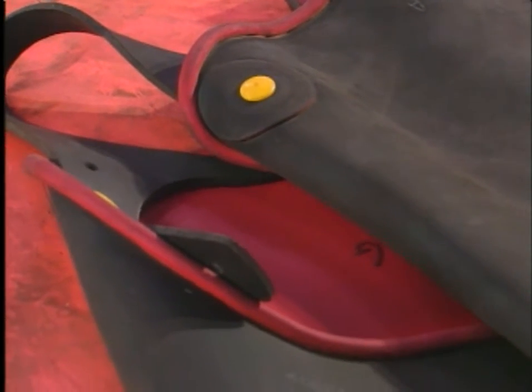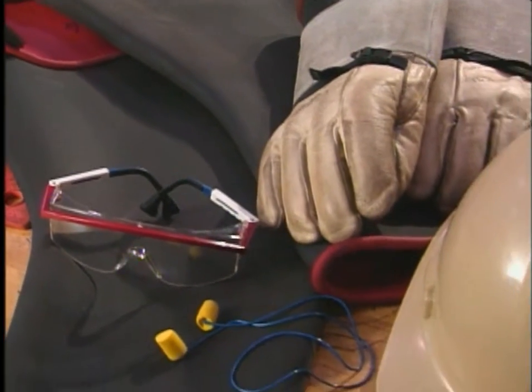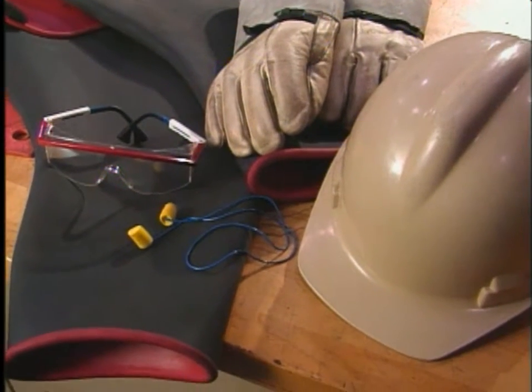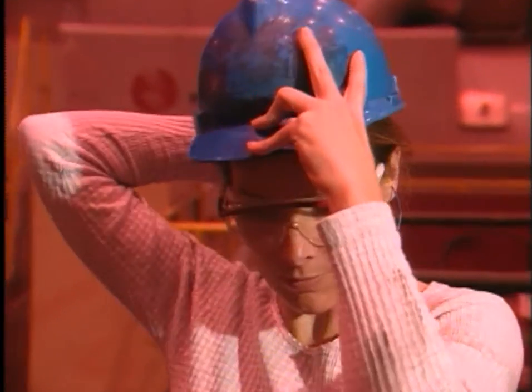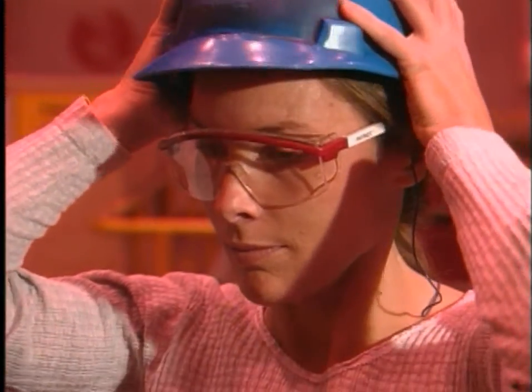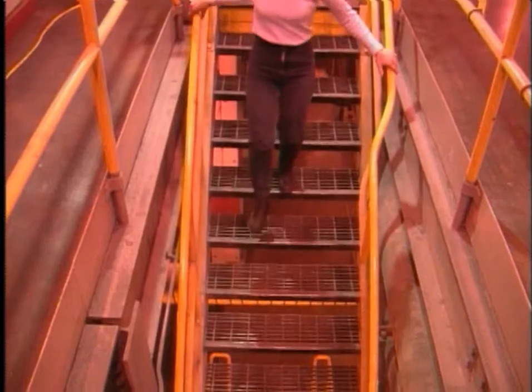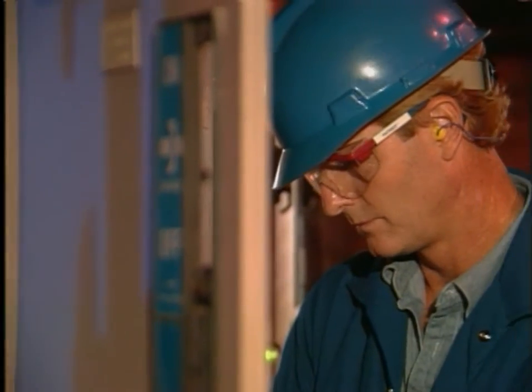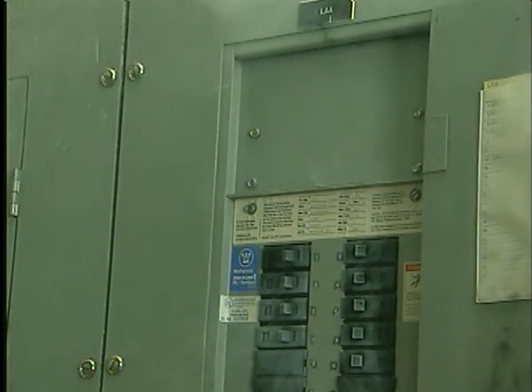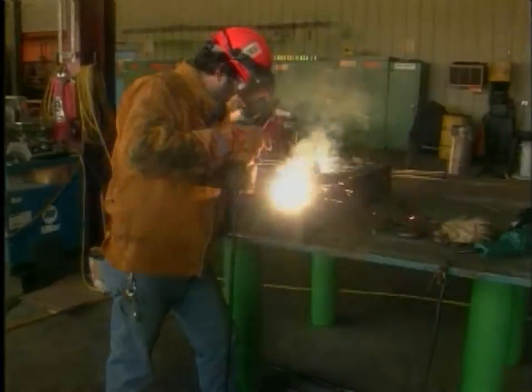Personal protective equipment is designed and made of materials to protect you in many ways. You might say this equipment goes a long way toward keeping the snake at a safe distance by protecting you against an unexpected strike. Non-conductive head protection protects you from electric shock, electrical burns, falling and moving objects. Be sure your hard hat is rated for the electrical hazard you face. Always wear eye protection when performing electrical work, especially on live circuits. A short circuit or a fault could result in not only flash burns, but hot molten metal particles can be thrown into your eyes and your face. A welder would not strike an arc without proper eye protection.